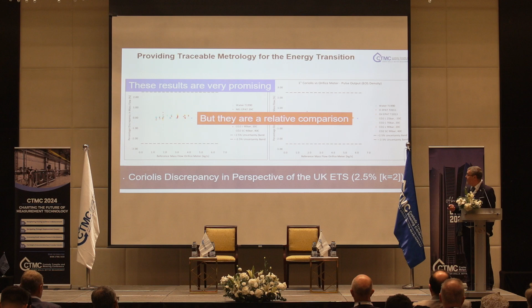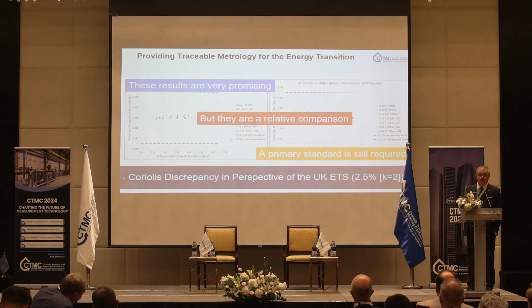Oh, sorry, just quickly there, you can see the water calibration, the oil calibrations at NEL, three liquid CO2 calibrations, and one supercritical calibration, just to make it clear that we're talking here about different fluids, different phases. So really quite good results, very promising. However, they are a relative comparison. All of this data assumes that the orifice plate is correct. They're just a reference to the orifice plate. There is no primary standard. They are a relative comparison. A primary standard is still required. So we're working towards that.